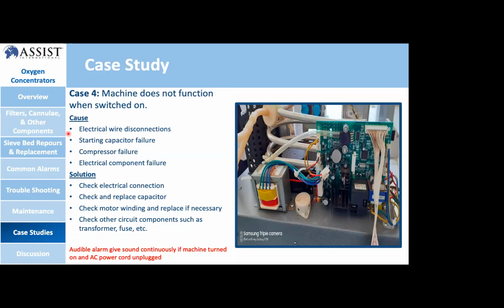The first one is electrical wire disconnection. That means maybe the power receptacle or power cords, or any wire connecting to electrical components. It may be the starting capacitor may fail, or the connection may be disconnected, or there is a loose connection of the capacitor. Since it is a starting capacitor, it starts the compressor to compress the air. If the capacitor fails, the machine will not start compressing the air.